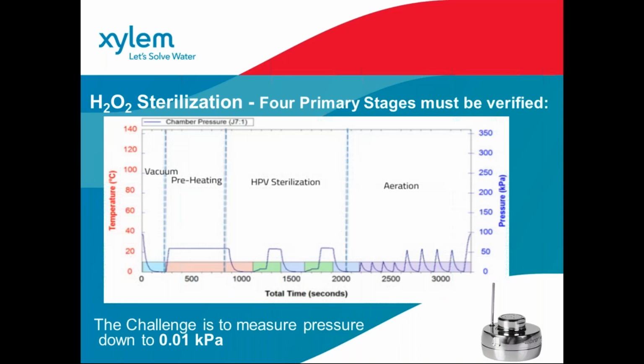So this is how you are supposed to measure your H2O2 sterilization in order for you to get an indication whether you have achieved the correct degree of sterilization. The challenge here in measuring this kind of process is how to measure pressure at a very low level, down to as low as 0.01 kilopascal, which is equivalent to 0.1 millibar. This is the most important parameter. As far as I'm concerned, this makes the whole process successful.